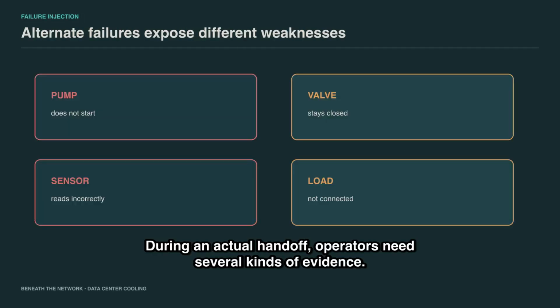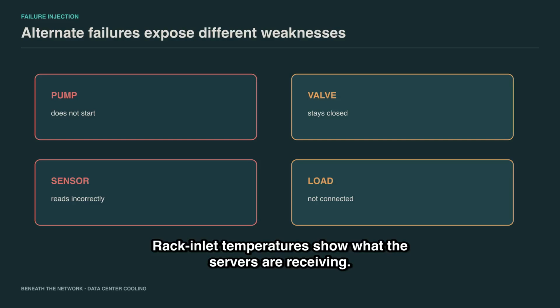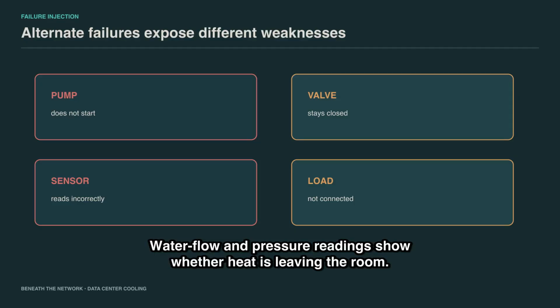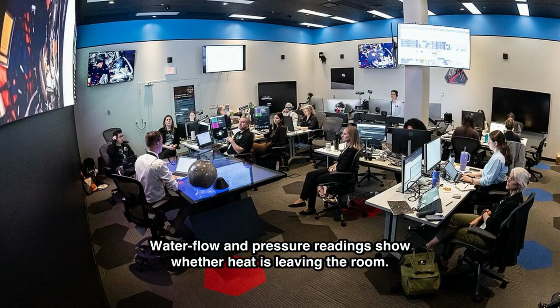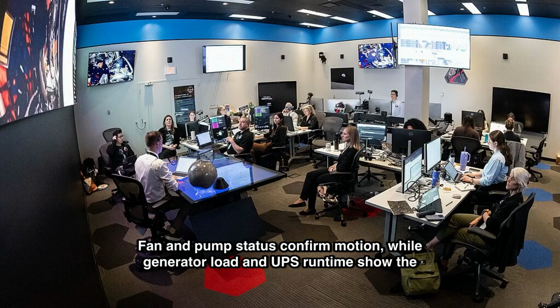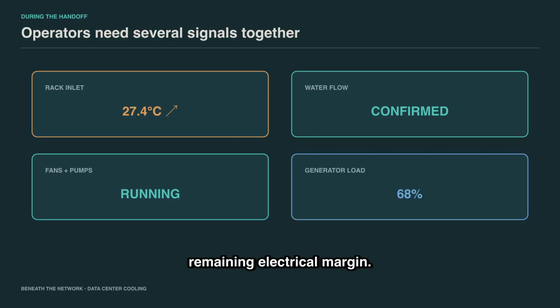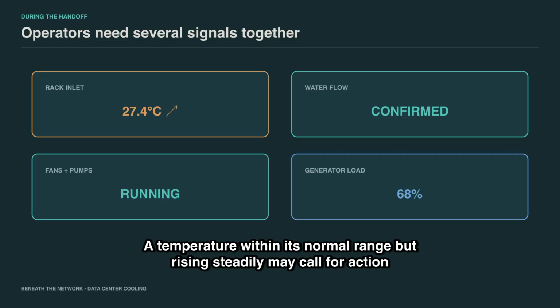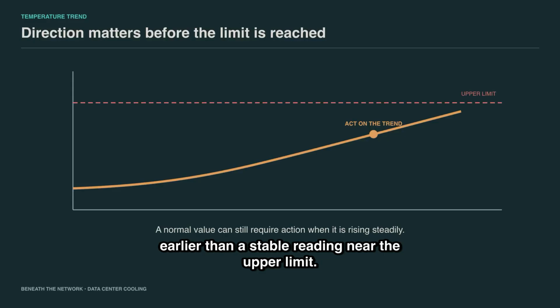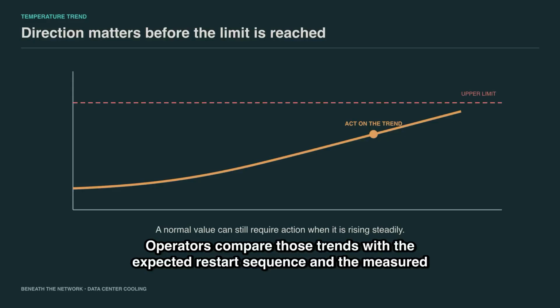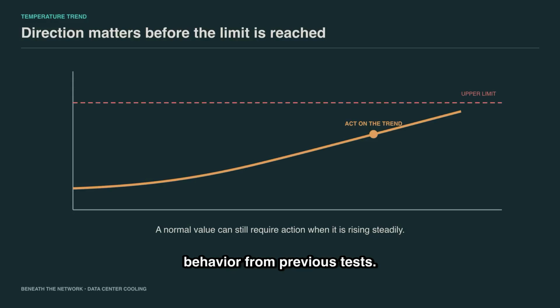During an actual handoff, operators need several kinds of evidence. Rack inlet temperatures show what the servers are receiving. Water flow and pressure readings show whether heat is leaving the room. Fan and pump status confirm motion, while generator load and UPS runtime show the remaining electrical margin. The direction of change matters. A temperature within its normal range, but rising steadily, may call for action earlier than a stable reading near the upper limit. Operators compare those trends with the expected restart sequence and the measured behavior from previous tests.